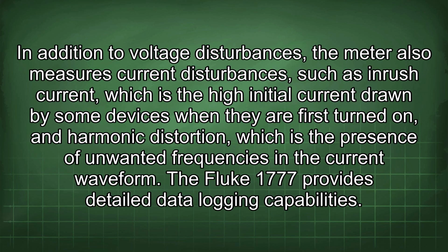In addition to voltage disturbances, the meter also measures current disturbances, such as inrush current, which is the high initial current drawn by some devices when they are first turned on, and harmonic distortion, which is the presence of unwanted frequencies in the current waveform.